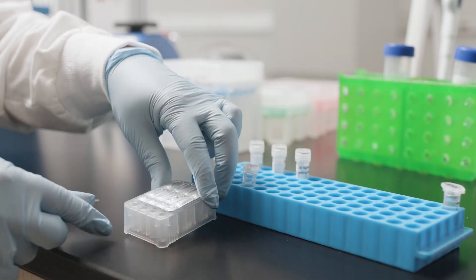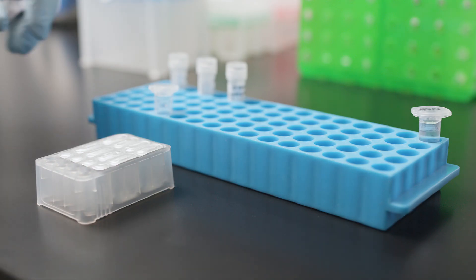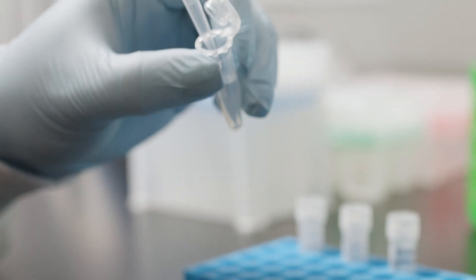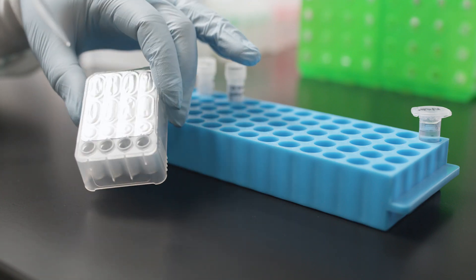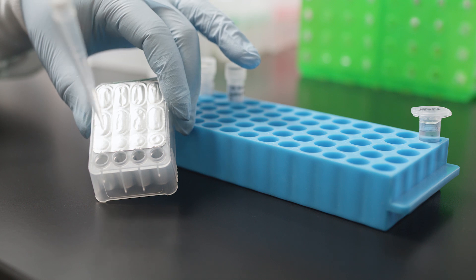The cartridge has four available sample wells corresponding to each lane of the flow cell. Carefully pipette at least 260 microliters of diluted libraries to the bottom of the designated sample wells, taking care to avoid introduction of bubbles.